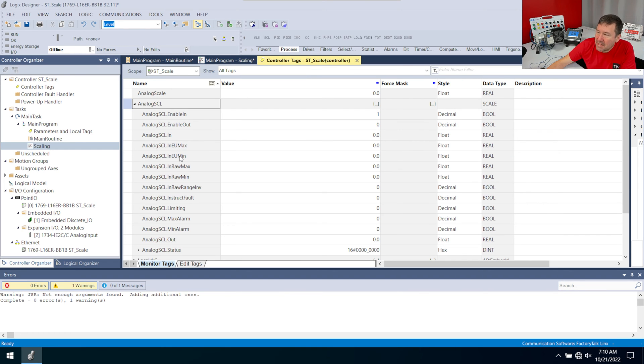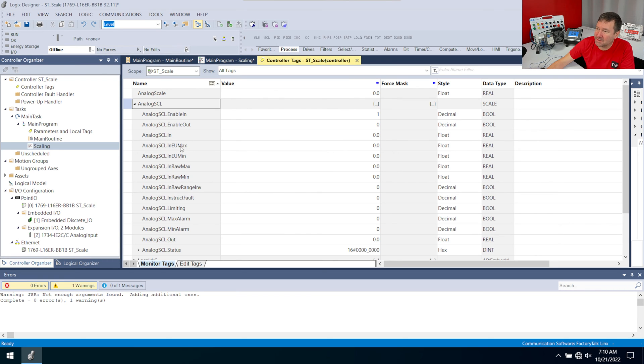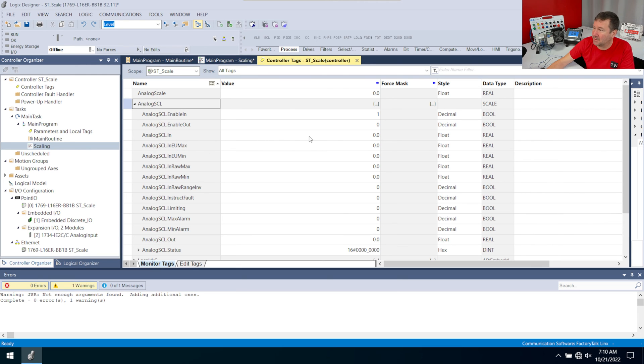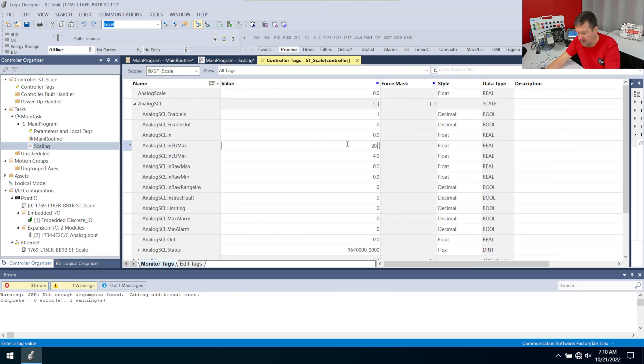So the EU min and EU max, that's actually the out. So right here, I've got analog SCL dot out. That is the scaling of that out. I really wish they would name this the out max and the out min or rename the other one EU. But I want this to be four to 20 milliamps. So I'm going to put four and 20.